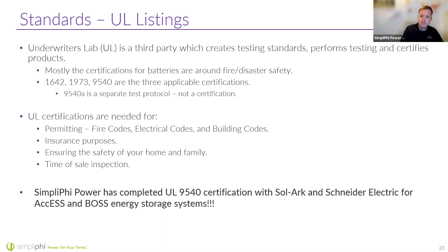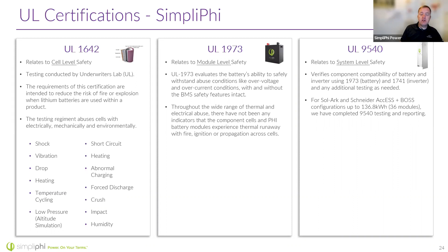I already broke this down a little bit. UL 1642 on the cell is similar to the UN test. They expose it to abusive shocks, abusive heating, impact, forced discharge, cycling it. We repeat those tests in the 1973. And if we're able to pass, then ultimately we get our 9540A.